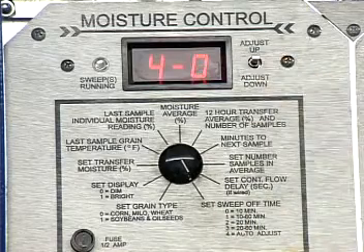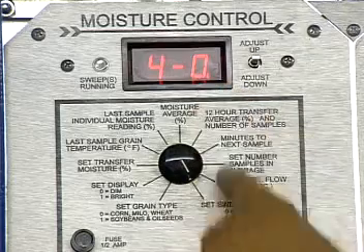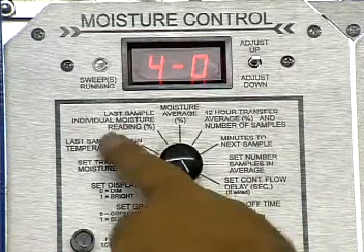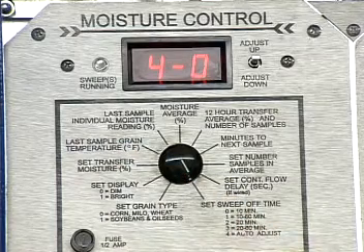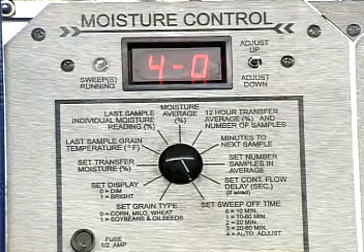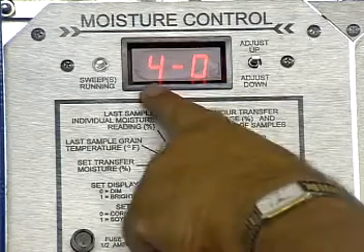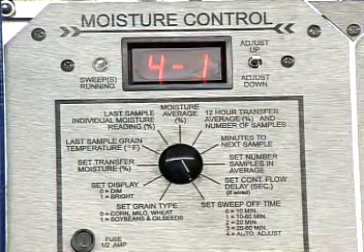Number 4 is the computer is going to automatically adjust it, but you want the computer to start at 0, which is 10 minutes. So if the computer sees a wet sample, it's going to wait 10 minutes to come back on. And if you read the instruction manual, it says that if it takes 5 samples in a row that are too wet, because it's on automatically adjust, it will switch itself to number 1.